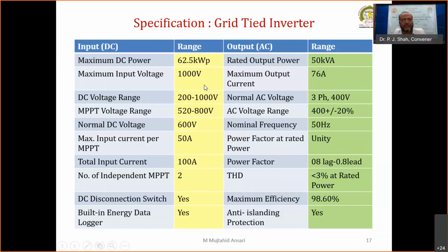The maximum voltage here is 1000 volt. It means that while designing the strings, the number of PV modules connected in series should be such that the voltage does not increase beyond 1000 volt, and similarly the voltage should not decrease below the minimum voltage, that is 520 volt. So the total series voltage should not be less than 520 volt, and should not be more than 1000 volt. Then and only then will it give the proper voltage on the input side, and we will get the proper voltage on the output side.